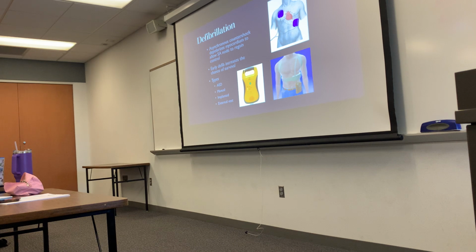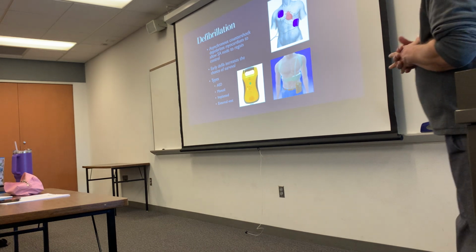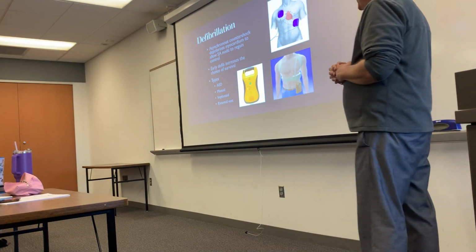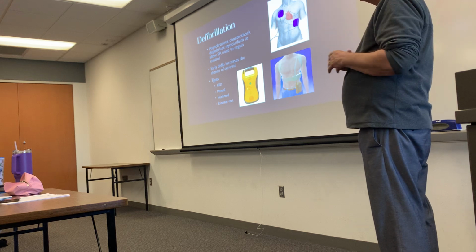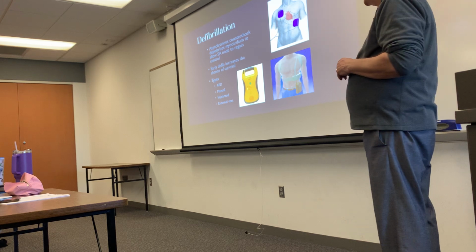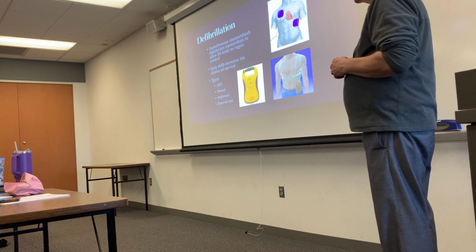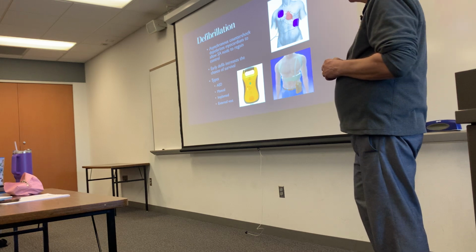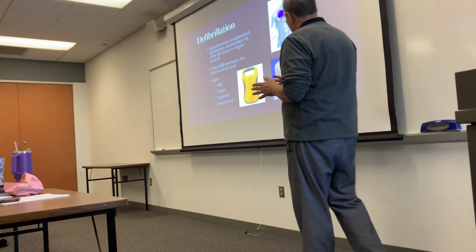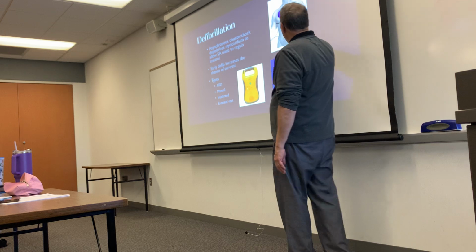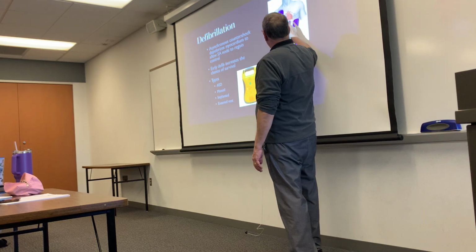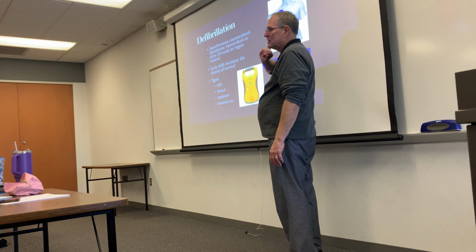All right, so your defibrillators these days are usually asynchronous, meaning they will tell you when to shock, right? And they're biphasic. There's not very many monophasic ones around. Biphasic means it's going to send the electrical impulse in both directions.